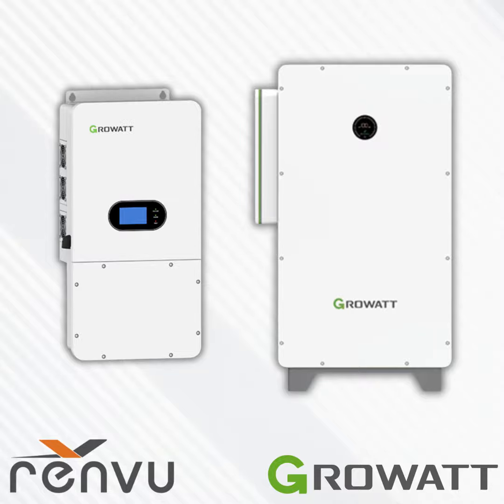So we just show this chart. This is something that we'll share with everybody after the presentation, but it's a good little reference to show which inverters are optimal with which batteries. For example, you can use the WIT 55 kilowatt inverter with an 86 kilowatt hour battery, but you'll be reducing your rate on that to 43 kilowatts, which is the max on the battery. So a little bit of derating in like off-grid application.